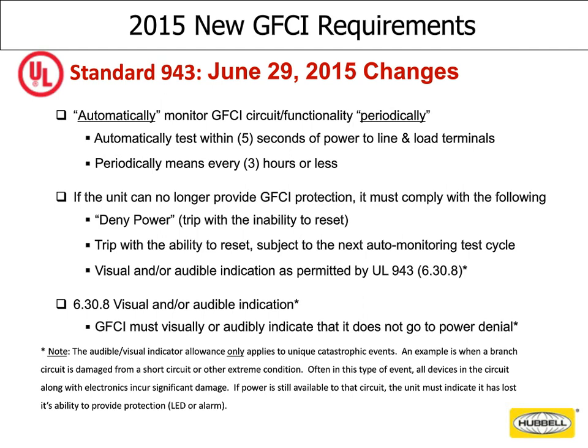And if it finds a problem, in 80% of the cases, it's going to trip the ground fault, and it's not going to allow you to reset that ground fault because it has found a problem with the circuitry, with the functionality of the ground fault. In about 20% of the cases, there's actually something wrong internally with the ground fault from a mechanical tripping standpoint, and it can't physically force itself to trip. In that case, the device, by UL requirement, must give you a visual or an audible indicator. So it may still provide power, but it's going to have either a flashing light or an audible alarm that tells you, hey, there's something wrong here. This receptacle is not protecting people, and you need to change it.